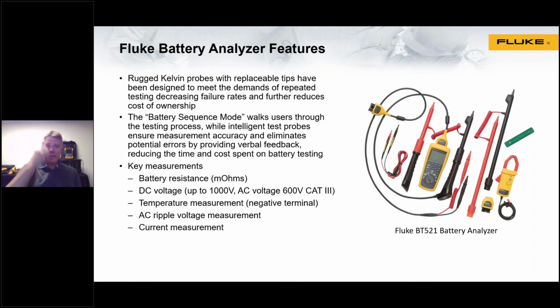The tester is also really an all-in-one. We talked a lot about battery resistance, that state of health measurement in milliohms. It, of course, makes that measurement, but it also captures DC voltage. For certain applications, maybe in switchgear, there might be hundreds of volts. This tool can actually measure up to 1,000 volts DC, and for three-phase UPS battery systems, you're working with perhaps 480 volt versions, so you don't need a separate multimeter. This has all the appropriate CAT ratings for transients.